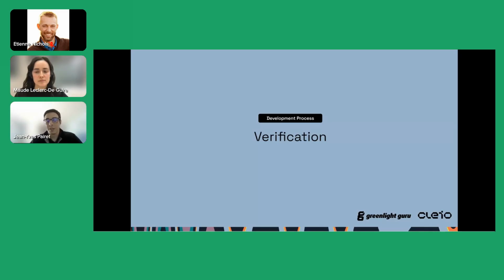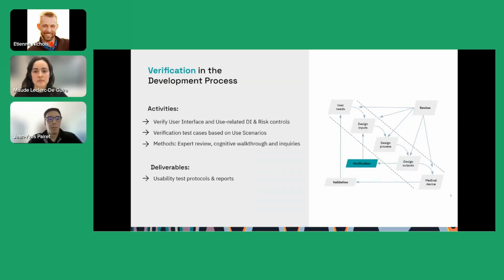So now let's address the verification step of the development plan. We discussed in the previous section how the design process is performed iteratively, using formative evaluation results to improve the design of the user interface. Once the design is completed and final, so we can talk about design freeze or production equivalent units, designers need to verify that the user interface meets all the established design inputs, including risk controls. Test cases are established generally using the data from the task analysis or use scenarios to test the user interface. Here again, we reuse all the available information. But other methods and tools can also be used, such as expert reviews, cognitive walkthrough, or inquiries.